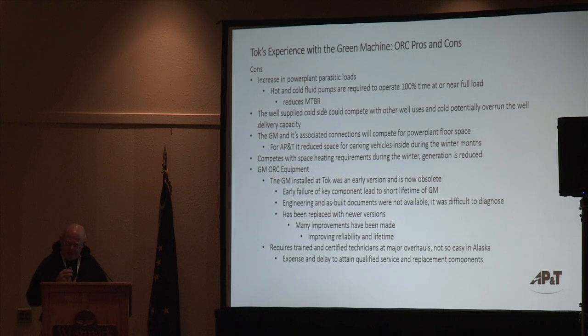The pumps for the machine run much harder than they do if the machine wasn't there. So the mean time between replacement of the pumps is going to be reduced. I mean, we're going to have to replace those more often. We used well water to provide the cooling side input. That was convenient and I think really worked well for the purposes of this installation. Moving forward, we have other demands on that well system, and it may not be the best way for us to move forward. We might go to a different type of cooling in the future.